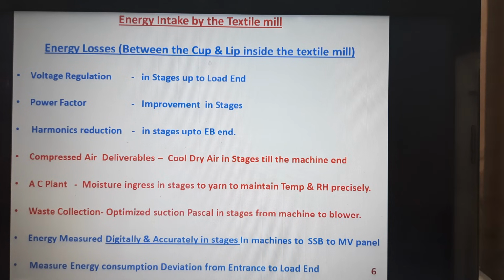Coming to the waste collection, optimized suction Pascal in stages. Let the machine deliver around 1600 or 2200 Pascals from the blower end. But what is needed at the card is around 600 Pascal. If you are keeping around 1000 Pascals at the header near the card, almost you lose around 20 to 30% of energy because the static pressure is more by 20%. If the static pressure is more by 20%, the power loss, kilowatt loss or the energy loss is around 33%. So let us try to concentrate on the static pressure, static Pascal in each and every aspect of the mill, and let us try to improve upon it. Wherever the energy is measured digitally and accurately in stages, definitely this will go in a big way to reduce the consumption of the mill as such.